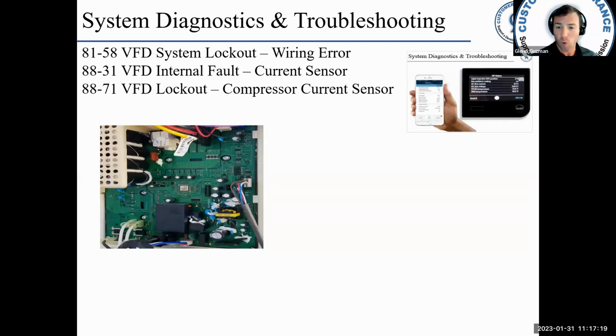VFD system lockout is a wiring error. That's 8158. 8831 is internal fault current sensor, and then 8871 compressor current sensor. The 8158 means the VFD sensed one or more of the compressor wires were not connected to the VFD. When can that happen? Maybe you replaced a compressor or did some kind of work inside the condensing unit and there are no wires on the compressor, or you're missing one of the wires, something like that.